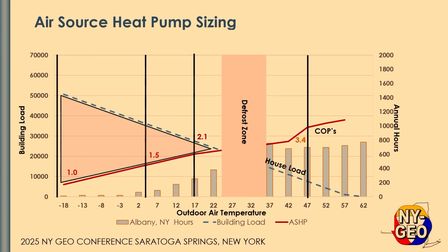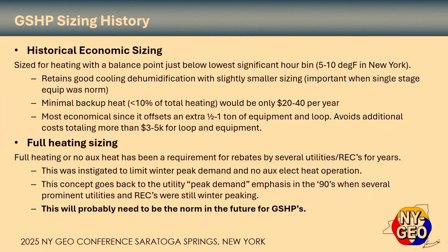So again, an air source heat pump sized for cooling typically results in this balance point being fairly high. And so that kind of summarizes a basic air source heat pump. We'll come back to all of that with the cold climate heat pump as well.